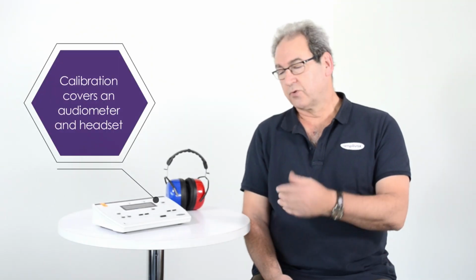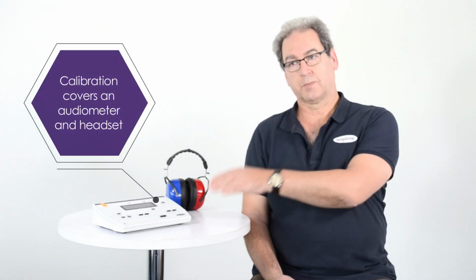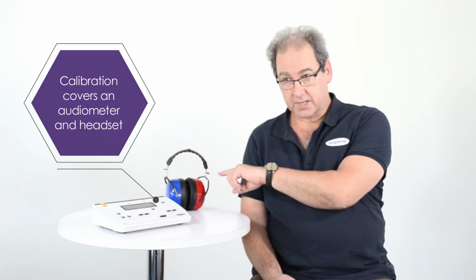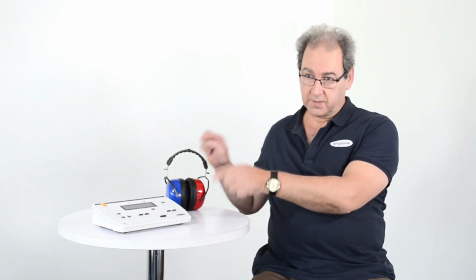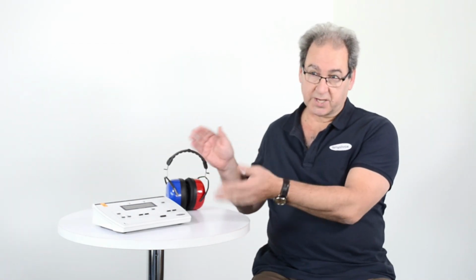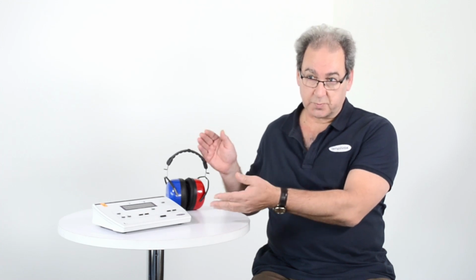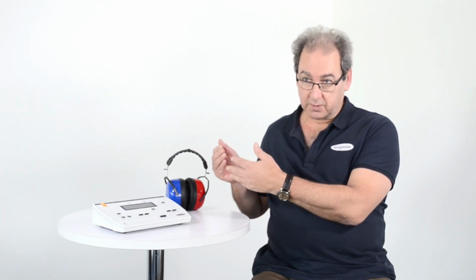Calibration for an audiometer is the audiometer plus the headset, and it's really important that these two items are actually kept together because they are a matched pair. If we change either one of those, we then have to do a complete calibration again.